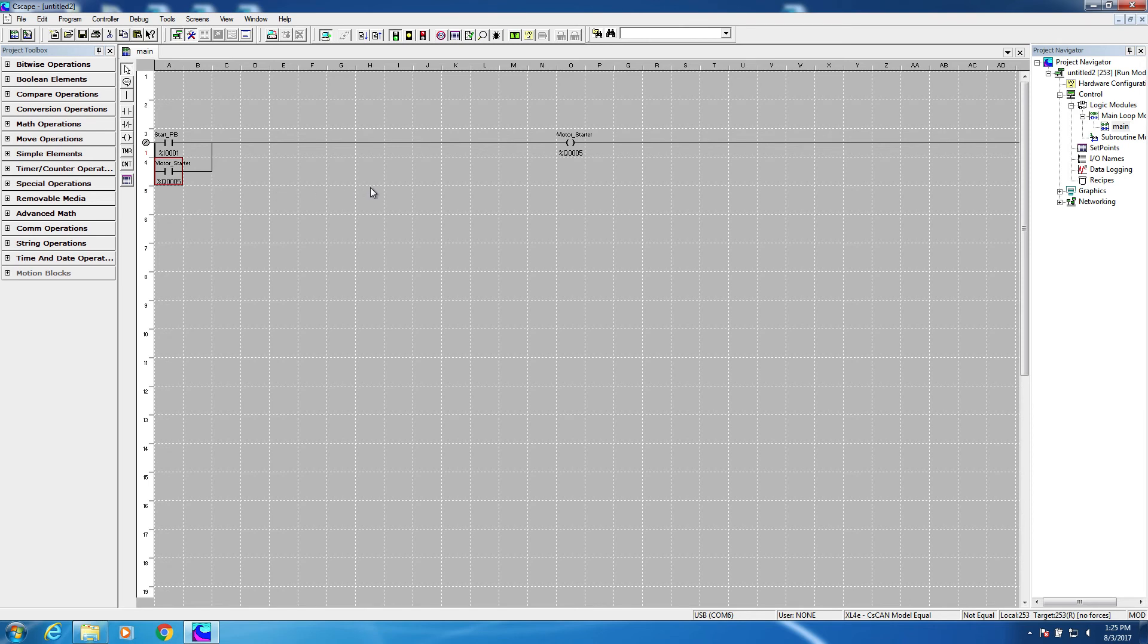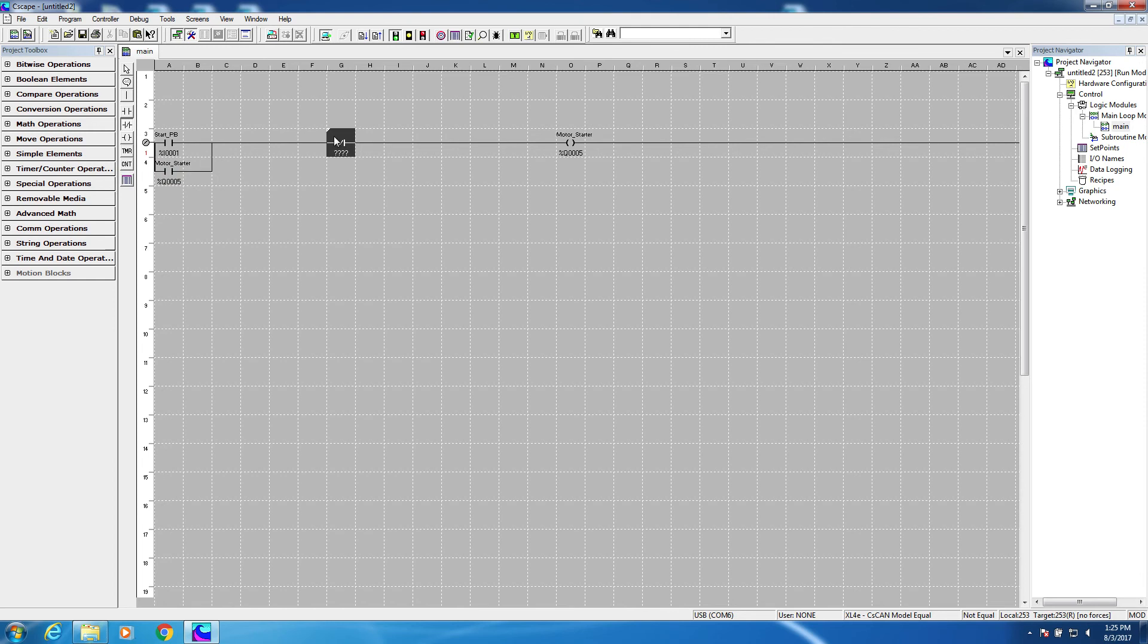Alright, there's one more problem with my circuit, and that is currently there's no way to stop the motor. Obviously, that's not good. So we're going to put in a set of normally closed contacts between the start area and the coil to allow a stop push button to stop the motor.